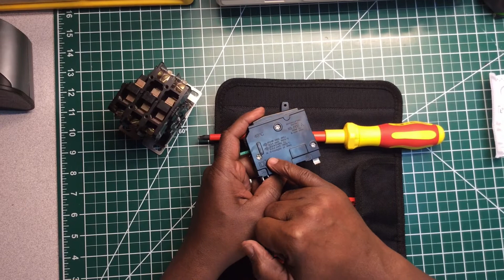That way you won't damage the conductor underneath, or break the strands if you're using stranded wire, because sometimes when you tighten too much it causes overheating, and if you don't tighten enough it also causes overheating. So it's best to follow the code. The code tells you to follow the manufacturer's instructions, and most of the time it'll be on the side of the breaker, like this breaker here. It says this is the Square D, 10 amp, 36 pounds for US, and it also says 4 Newton meters, NM. I don't know if you guys can see it, but it says 4 Newton meters, NM, and that's what that acronym stands for.